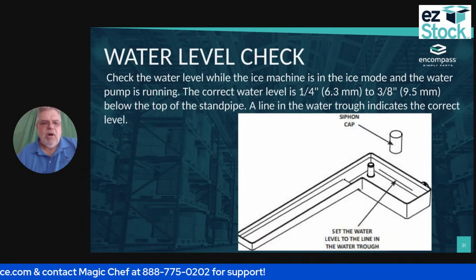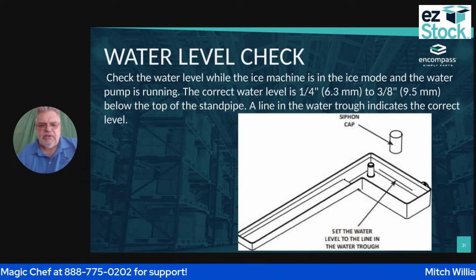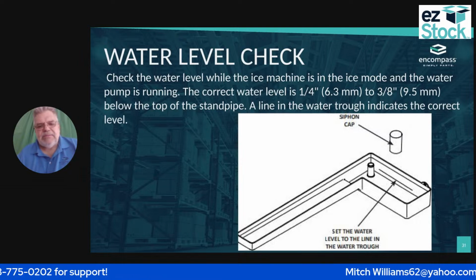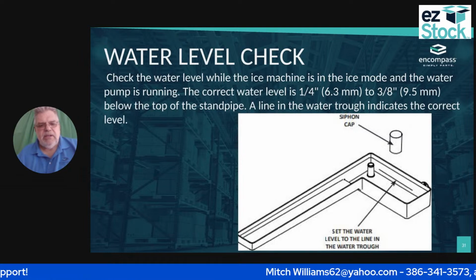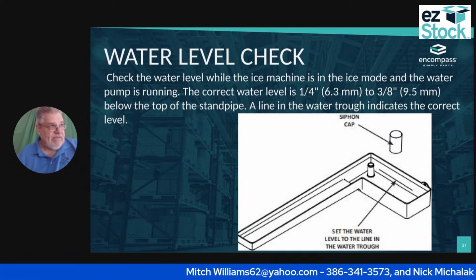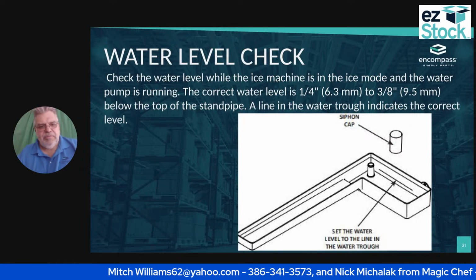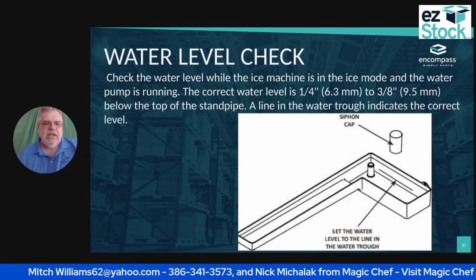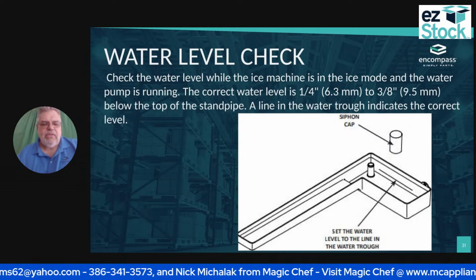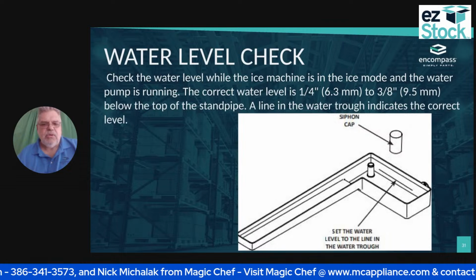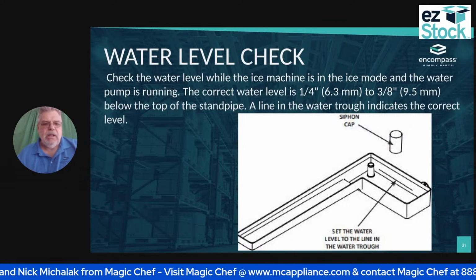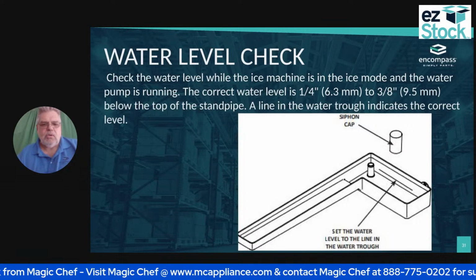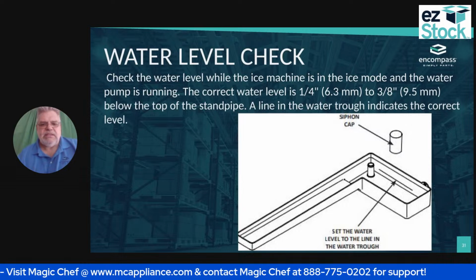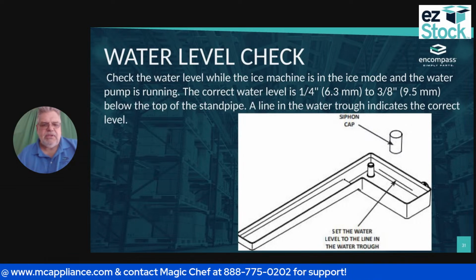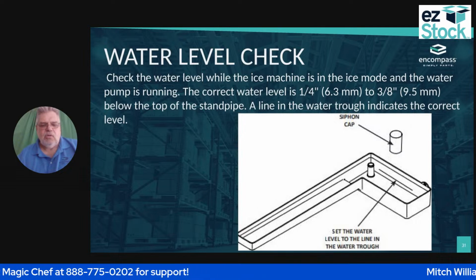Okay, my water level check right here. There's the siphon cap. Nine times out of ten, somebody's probably pulled that siphon cap off, but it'll work without it. So check the water level while the ice machine is in the ice mode. The water pump is running. The correct water level is 1/4 of an inch to 3/8 of an inch below the top of the standpipe. The line on the water trough indicates the correct level.